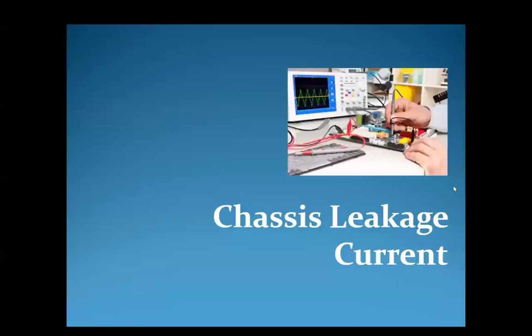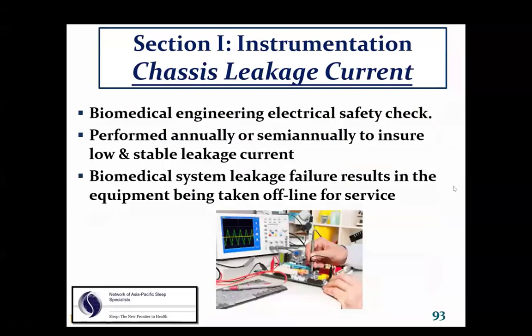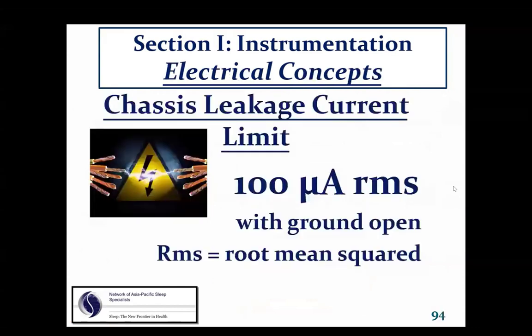Chassis leakage current. Now, that's a weird term. It's a biomedical term, and most of us don't relate to that term. What chassis leakage current is, it's the biomedical engineering electrical safety check. It's performed annually or semi-annually to make sure that there's no current coming out of that equipment that might harm the patient. Every time you touch your keyboard, every time you touch your TV set, there is current flowing into your body. But there has to be a safe limit and an unsafe limit. We can't entirely control leakage current. So the biomedical engineering department tests the equipment either once or twice a year, and if it exceeds that, the equipment must be taken offline and sent back to the manufacturer to be repaired.